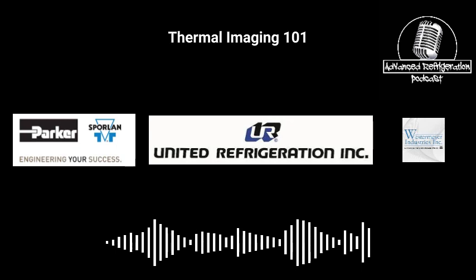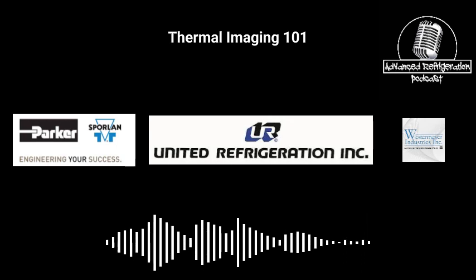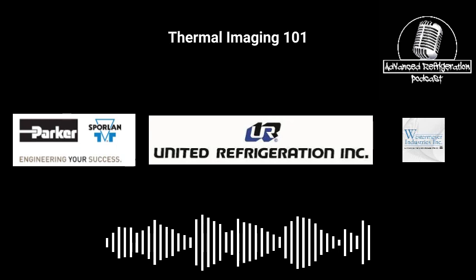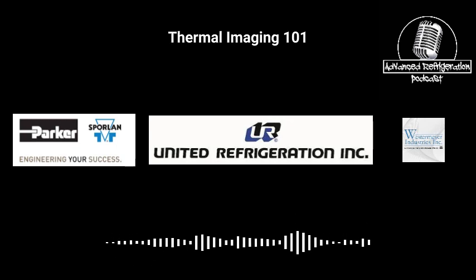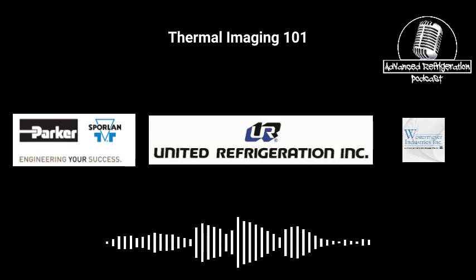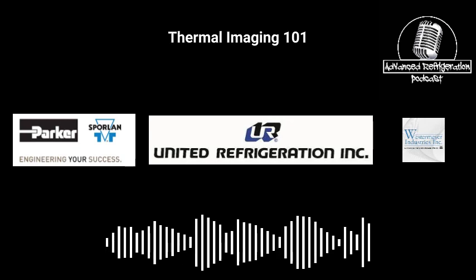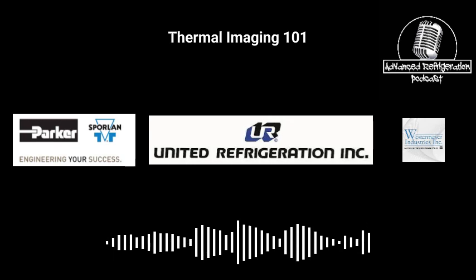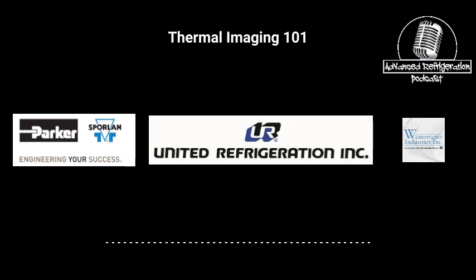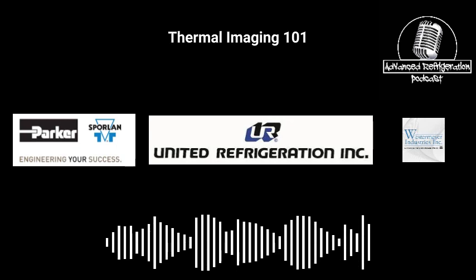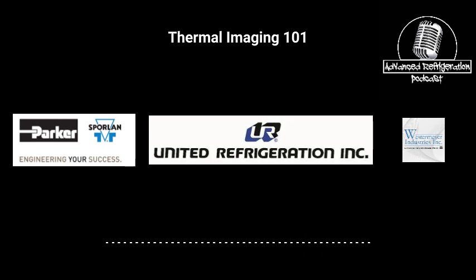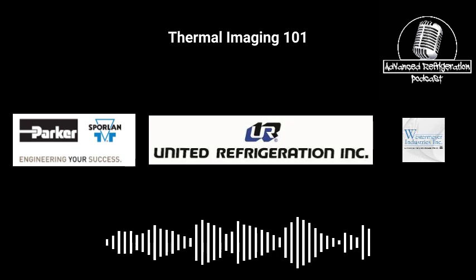You can shoot a hot gas bypass valve and see if it's feeding, or the receiver repressurization valve and see if that's feeding when it's really not supposed to. That's pretty cool. Let's see if I can find a picture of it. I have a picture of an undercharged headmaster, and you can see the whole bottom of the valve is red as it's injecting hot gas into the top of the receiver, and the whole top of the receiver is red. You can see that whole operation of the headmaster, so in a sense you could almost use it to troubleshoot.